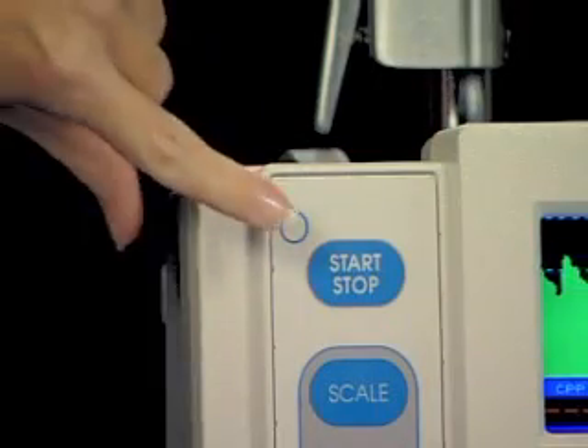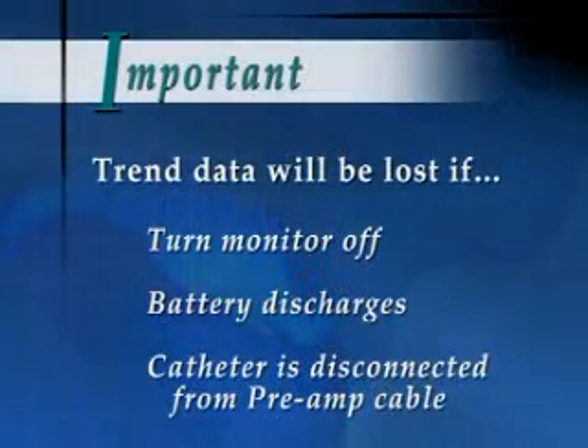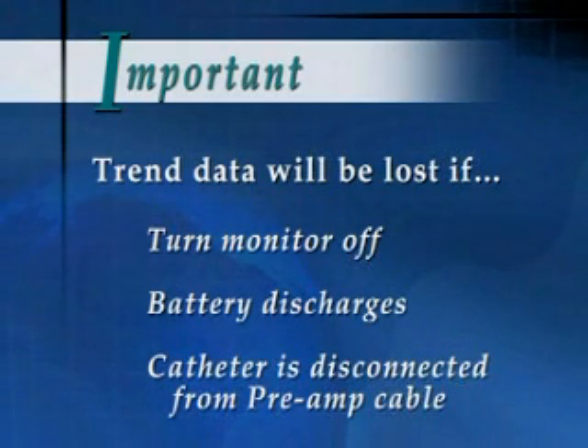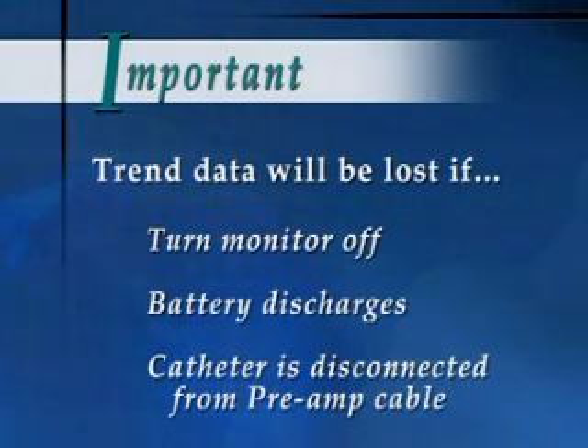To clear the trend, turn the MPM-1 off momentarily. It is important to remember you will lose your trend data if you turn off your monitor, the battery completely discharges, or the catheter is disconnected from the preamp cable.